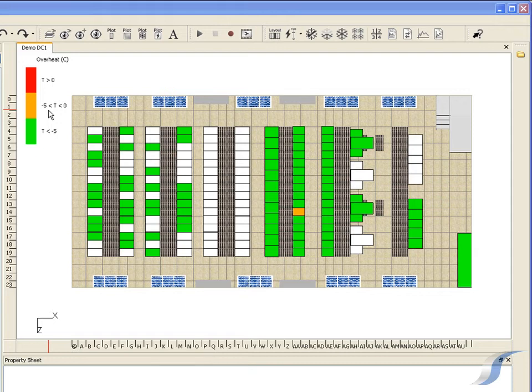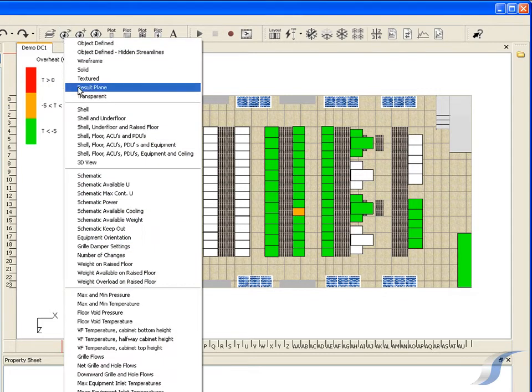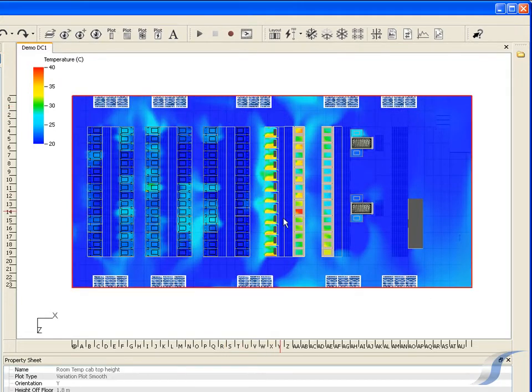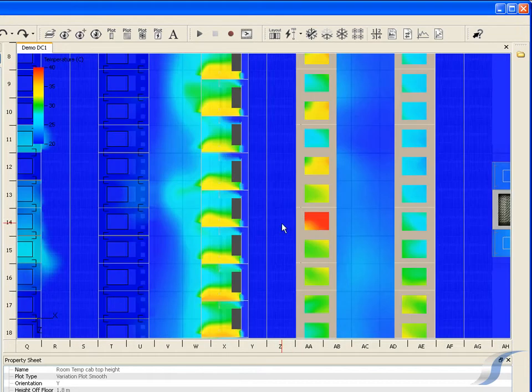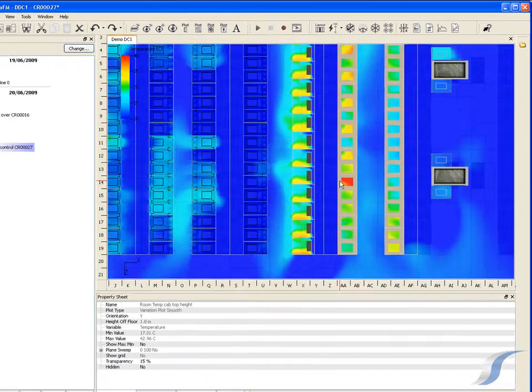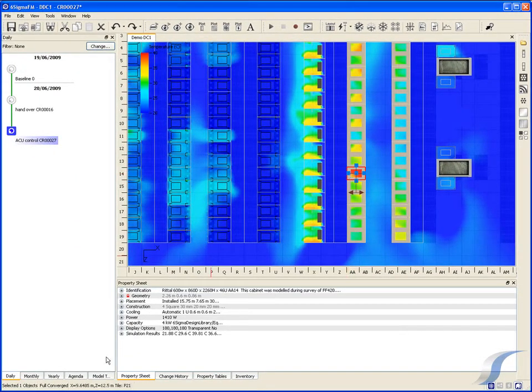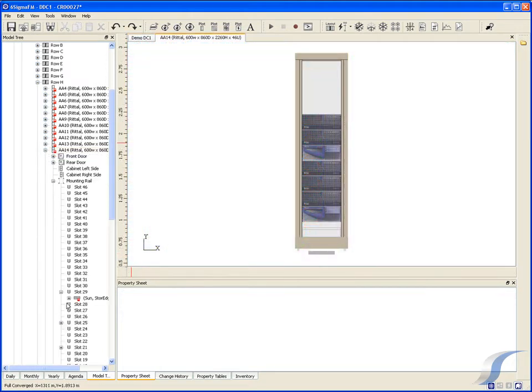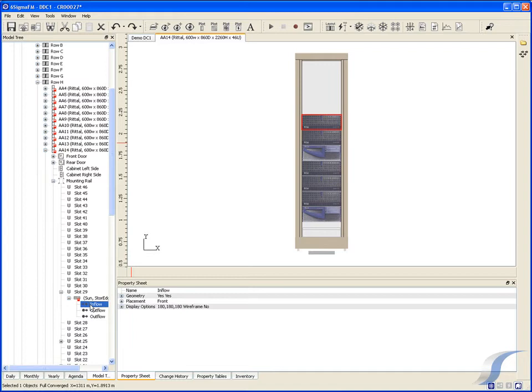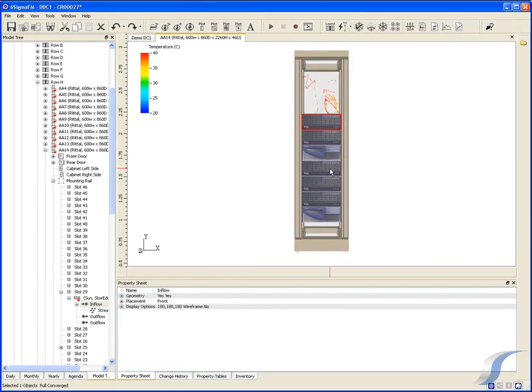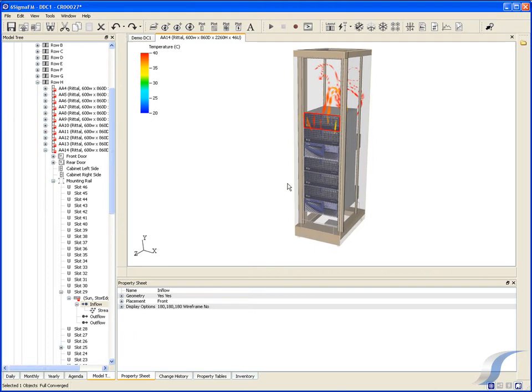Is there a better way to avoid overheating and regain the 5 degree safety margin? We can see that the temperature in the cold aisle in front of the overheating cabinet is around 18 degrees C, which is acceptable. This means the overheat must be an internal cabinet problem and not a room-level problem. By adding streamlines to the inflow of the overheating equipment, we can see that air is recirculating within the cabinet — the hot equipment exhaust is being taken straight back into the inflow rather than exiting the cabinet and returning to an ACU.